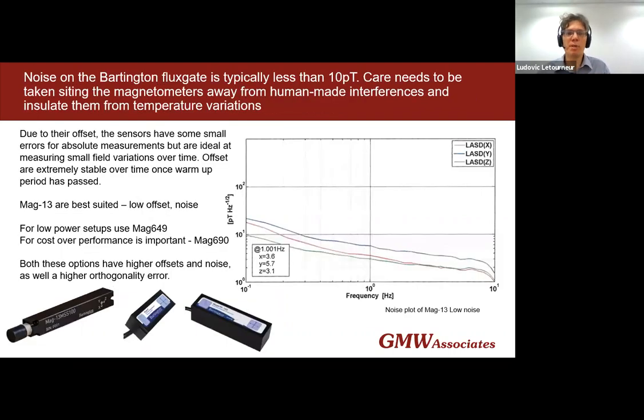So now if we look a bit more in detail at the Bartington fluxgate sensors, there's quite a range of sensors, and most of them will offer noise levels in the tens of picotesla or less. So they are extremely precise instruments, and they can detect very small variations from things like vehicles at a fairly long distance. So one of the elements to take into account when setting up a network of magnetometers is finding a suitable site away from man-made interferences, railroads, roads, fences, or anything that is ferromagnetic and subject to movement. Mike will touch on that on the hardware side of things.